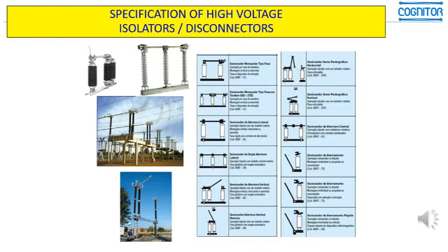I would say that the only requirement which is not covered by isolators is the breaking capacity of circuit breakers. Now, usually the disconnectors are in series with some circuit breakers, so they should attend most of the requirements of circuit breakers except the breaking capacity.